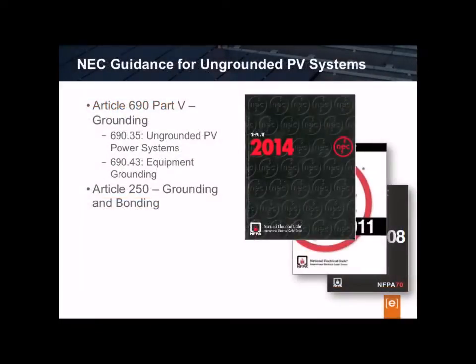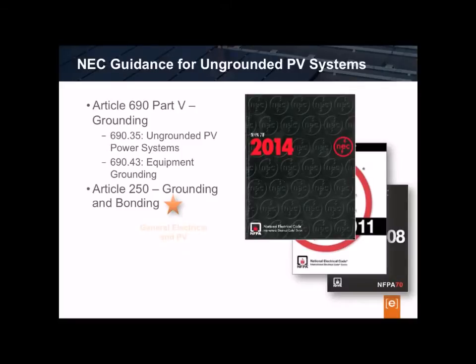However, the National Electrical Code does provide guidance for implementing ungrounded PV arrays, which carry additional safety benefits. Article 690.35 of the NEC covers ungrounded PV power systems, and Article 690.43 describes equipment grounding requirements. Additionally, Article 250 gives additional details on grounding and bonding requirements for general electrical, but relevant to PV power systems.